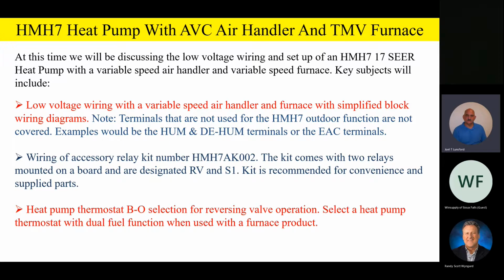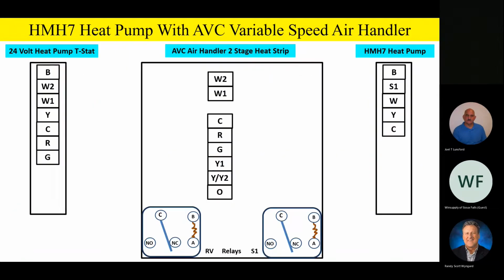Now, guys, please remember this heat pump thermostat, it has a BO selection for reversing valve operation. That stays the same. And always remember, select a heat pump thermostat for dual fuel function when you use it with any furnace product. So let's take a look at this. So let's take a look at an AVC air handler.